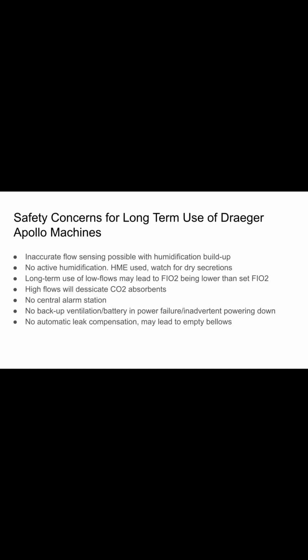And then also just to be aware that there is no automatic leak compensation with these anesthesia machines. So with all these extra components we're adding, like viral filters and inline suction, there may be small leaks, and over time that may lead to empty bellows in the machine and diminishing tidal volumes. So keep an eye on tidal volumes. Hopefully with the higher flows, we will avoid some of this, but we need to be mindful of leaks in the circuit.